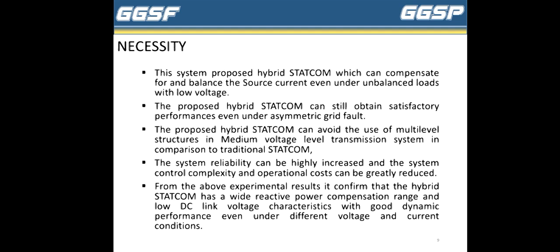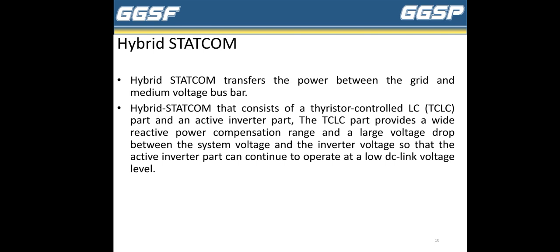Next is the hybrid STATCOM. Hybrid STATCOM transfers power between the grid and the medium voltage bus bar. The hybrid STATCOM consists of the thyristor controlled LC, this is TCLC, part and an active inverter part. The TCLC part provides a wide reactive power compensation range and a large voltage drop between the system voltage and the inverter voltage, so that the active inverter part can continue to operate at a low DC link voltage level.